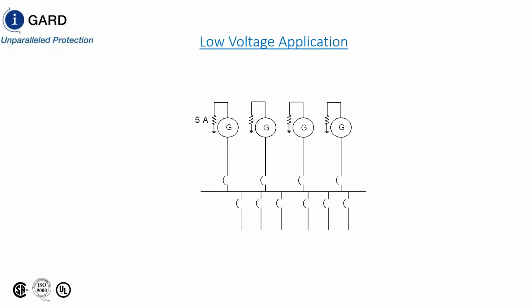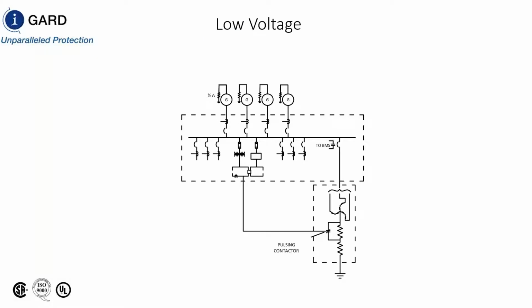So an alternative to this is to put a zigzag transformer on the bus and limit the fault current on each generator to a low value. In this particular case, we chose 0.5 amp. Same concept, because we just need to overcome the capacitive charging current up until this breaker. So we still protect the generator for single phase to ground faults before the generator breaker is closed and after it's open due to an internal fault.